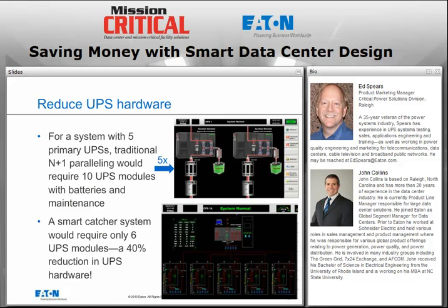And then what happens is if there's a problem with one of those primary UPSs, it switches to its bypass. Now, as opposed to a regular UPS system, bypass typically means utility power, but here we're drawing UPS protected power from the reserve system. That's how the load is never exposed to utility. So I just wanted to remind everyone that the examples we're showing aren't the only type of configuration to do it. As a consulting engineer or a facilities engineer, there are a lot of liberties you can take. The main part of what enables all this, as Ed's talking about, is that programmable SCADA system. That's the brains of the whole operation, controlling how the breaker operates.